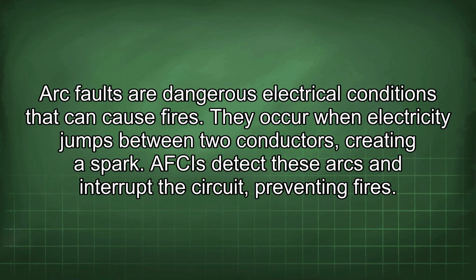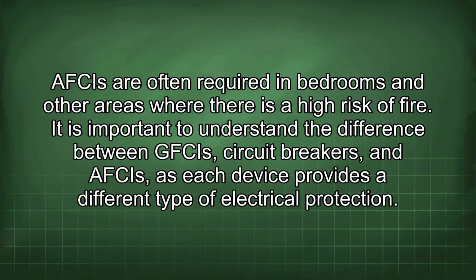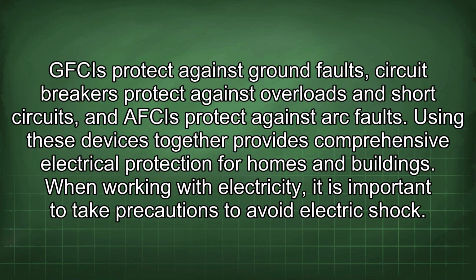AFCIs detect these arcs and interrupt the circuit, preventing fires. AFCIs are often required in bedrooms and other areas where there is a high risk of fire. It is important to understand the difference between GFCIs, circuit breakers, and AFCIs, as each device provides a different type of electrical protection. GFCIs protect against ground faults, circuit breakers protect against overloads and short circuits, and AFCIs protect against arc faults. Using these devices together provides comprehensive electrical protection for homes and buildings.